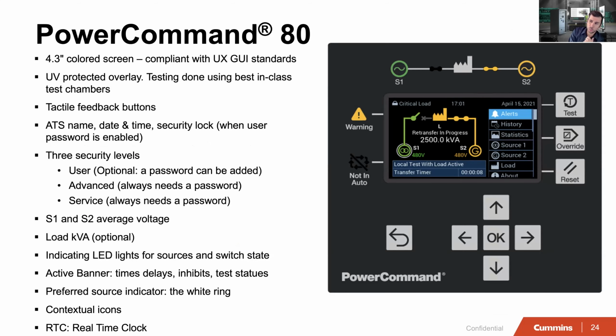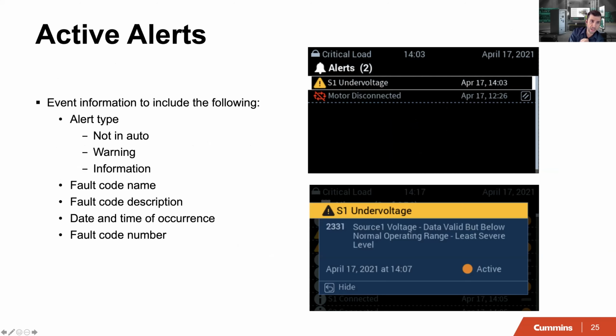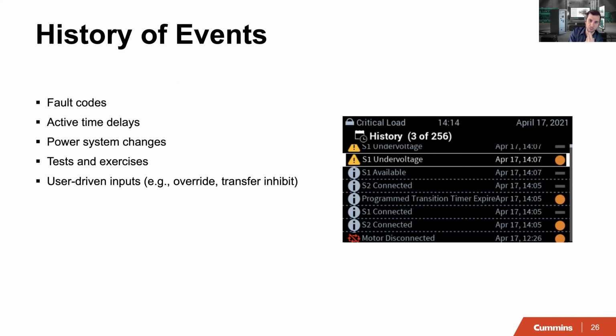The PowerCommand 80, which is the control and the transfer switch. Again, all the important data that you need are readily available for you to see which source is available and which source the load is connected to. A banner tells us any active alarms or any active timers, if there's a test that's happening on the transfer switch. Load data as well. Active alerts, the name of the fault, fault code, fault description, date and time of the occurrence, and all the faults go into a fault history.